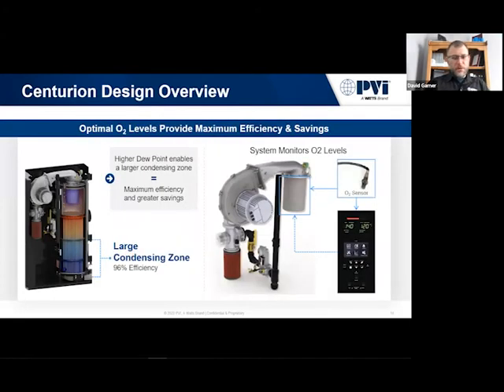The way the O2 itself works is we have an O2 sensor mounted right on top of the burner. It's in the combustion chamber, and it's looking at real-time O2 levels. Even when we do startup on the equipment, we have a test port that's kind of downstream. This is actually looking at what's happening inside the combustion chamber. The controller itself, we can control that blower down to a single RPM. And that's how we trim the system, is we already have what we know is the correct air-fuel ratio.